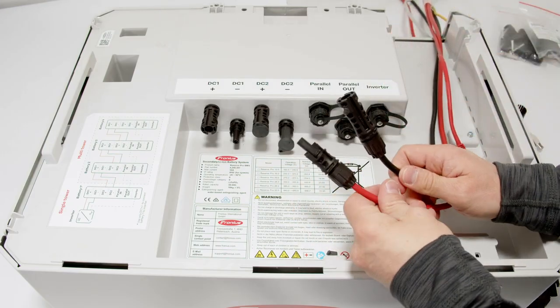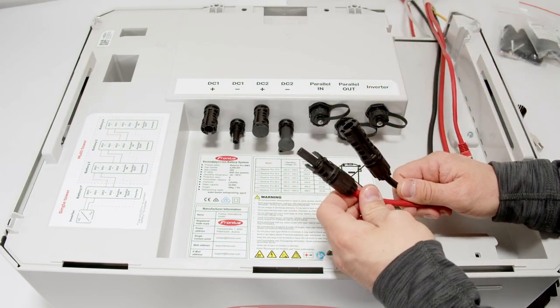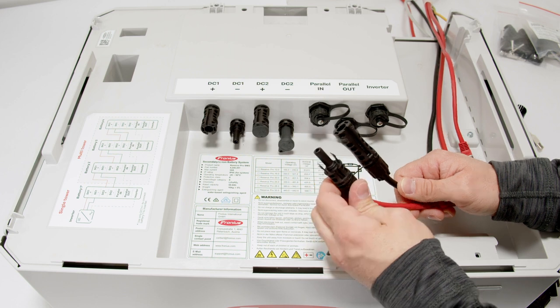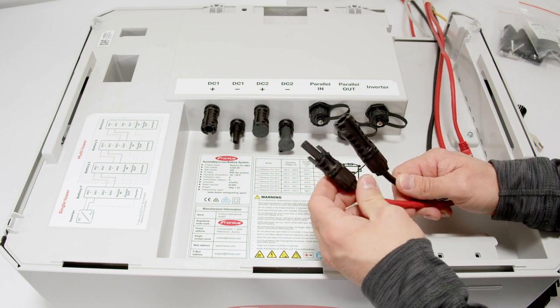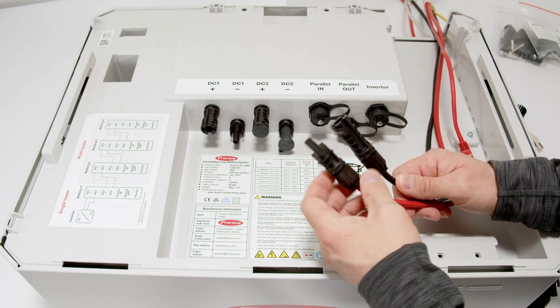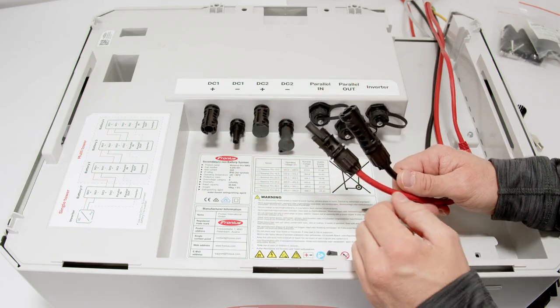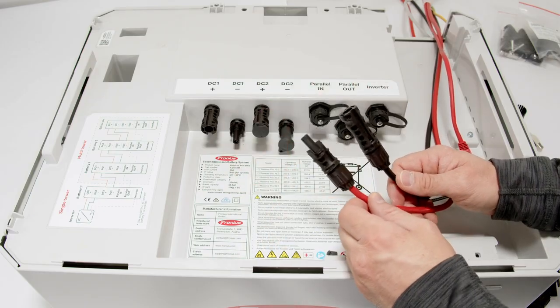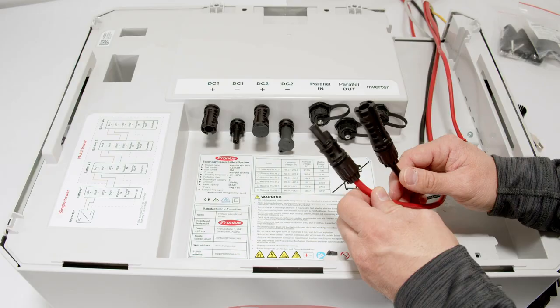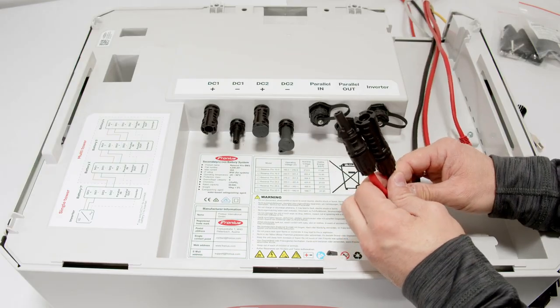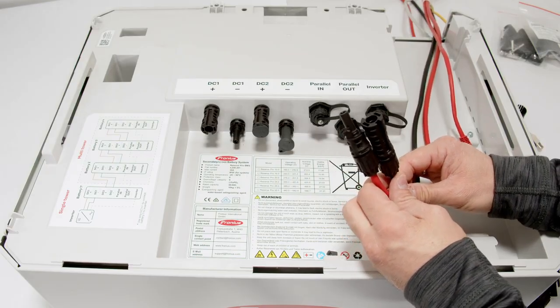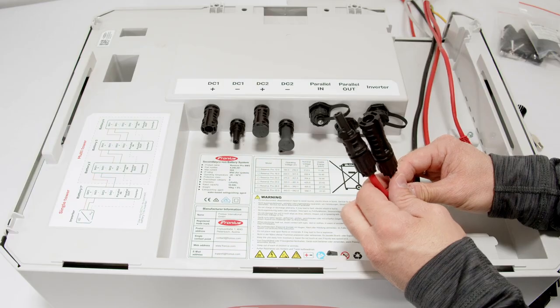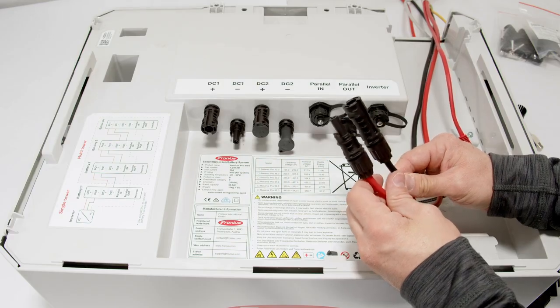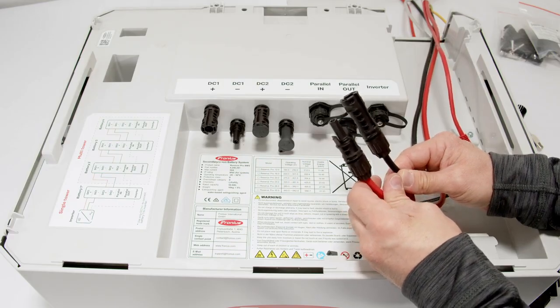For the DC connection, you please take our scope of delivery MC4 plugs EvoStore. So these are plugs from Stäubli that are 90-degree tilted to a normal MC4 plug. So that means that they can be only used for battery connection. Please also note, in scope of delivery there are 2 different plugs. There is one plug for a 6 square millimeter cable and one plug for a 10 square millimeter cable.